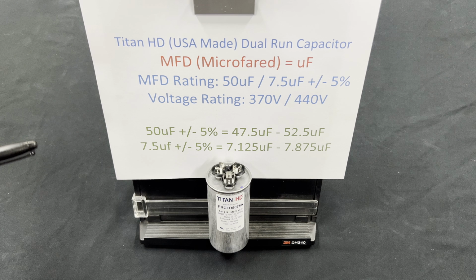The voltage rating on a capacitor is the max voltage that a capacitor is able to handle. A general rule of thumb says you can replace a capacitor with a higher voltage rating, but you never want to replace a capacitor with a lower voltage rating. Most of the replacement capacitors I keep with me are rated for both 370 and 440 volt AC.